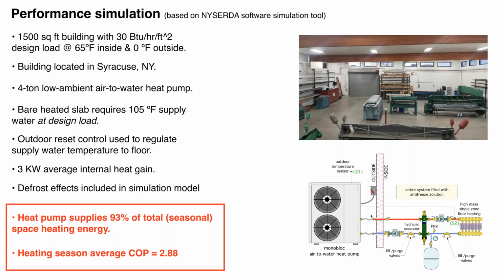Now, I'm sure some of you are wondering, how do these air-to-water heat pumps perform in a cold climate in this kind of a setup? Well, last year we worked on a project for the New York State Energy Research and Development Authority, NYSERDA, and we developed a pretty detailed software simulation for air-to-water heat pumps with a variety of climate zones. Because it was a NYSERDA project, these climate zones are, at present, just New York State locations, but they vary from very cold, 8,000 degree days, down to, let's say in Brooklyn, I forgot, 5,500 degree days, something like that. So we've run this simulation, and I ran it for Syracuse, which is kind of dead center in the state. It's about 6,700 degree days.